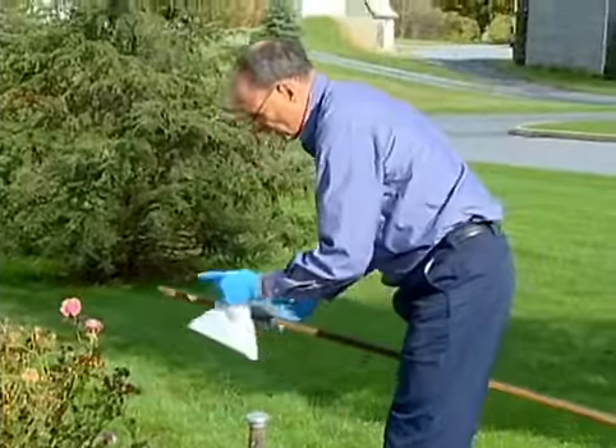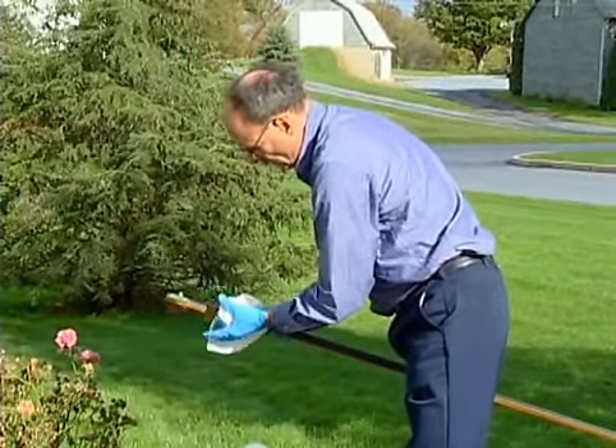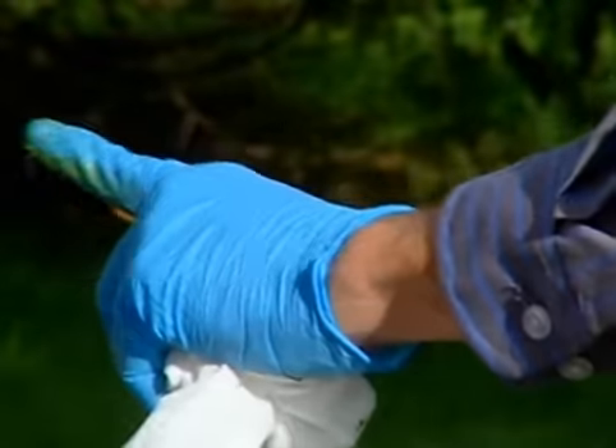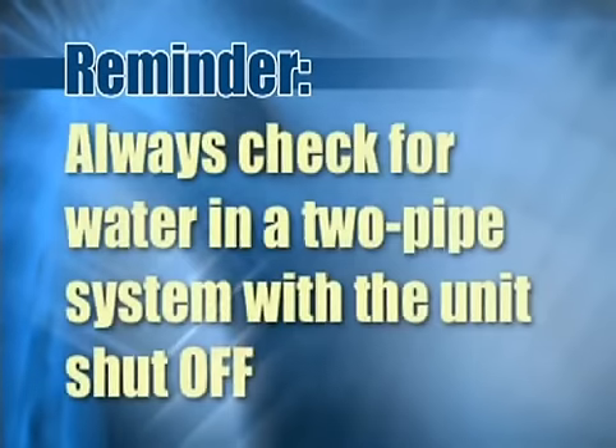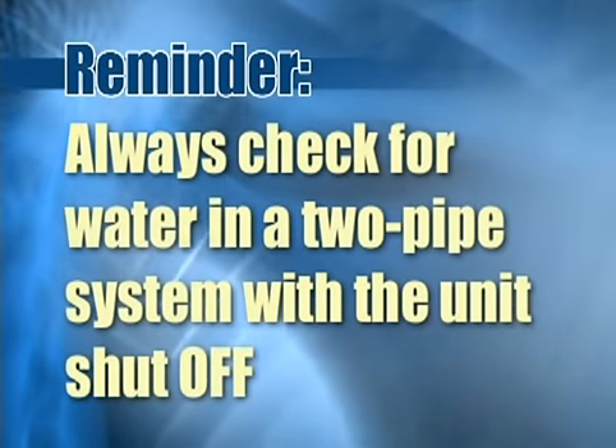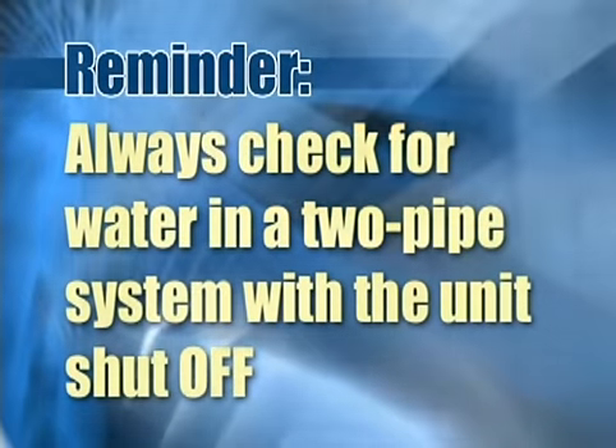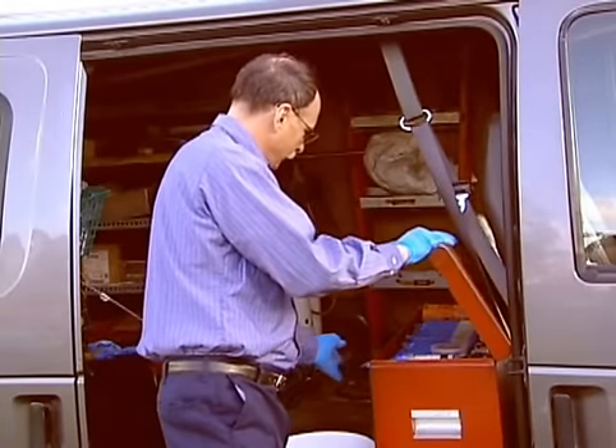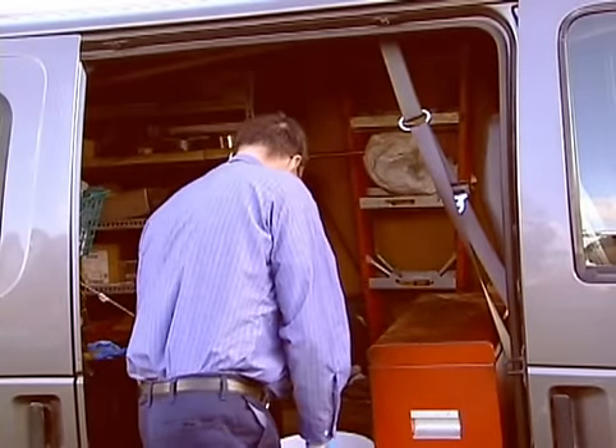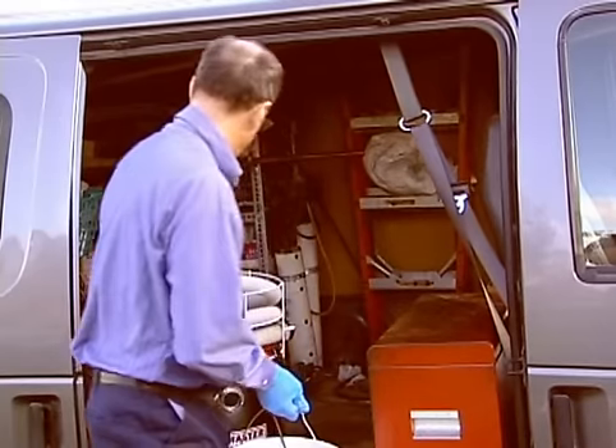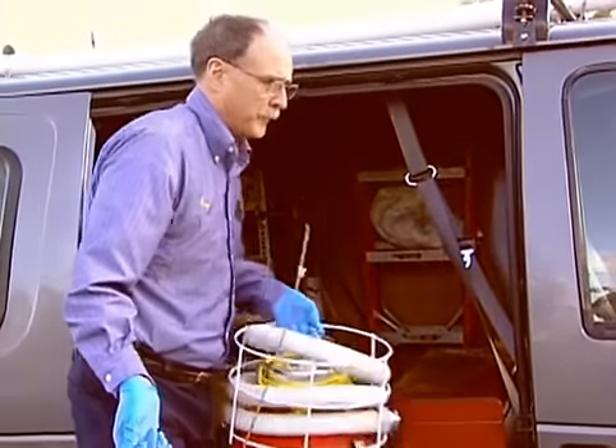If the tank is buried, measure the oil level with your measuring stick and use water-finding paste to make sure there's no water. Remember, always check for water in a two-pipe system with the unit shut off. When you've completed your outside inspection, gather your vacuum cleaner, brushes, additional tools, a garbage bag, and replacement parts from your truck.